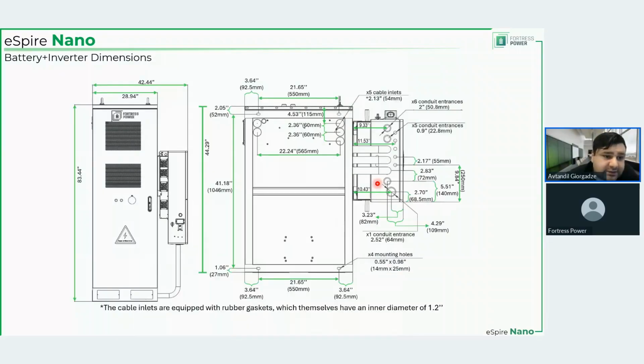Dimensions. So as you see, the unit itself is quite tall, 83.44 inches. It's also quite wide, 29 inches almost, with the inverter even more, 42.44 inches. This is the base of it, as you see here. All the distances are given here. Just a small comment, the cable inlets are equipped with rubber gaskets, so that's right here. It's 2.36 inches as such, but that rubberized part has an inner diameter of 1.2 inches, which would be plenty. Also, the mounting holes that I was talking about, 4 of them, they are over here. And I mean, other dimensions that you might find relevant. Again, this will be in the documentation included. That's actually where I got this from.